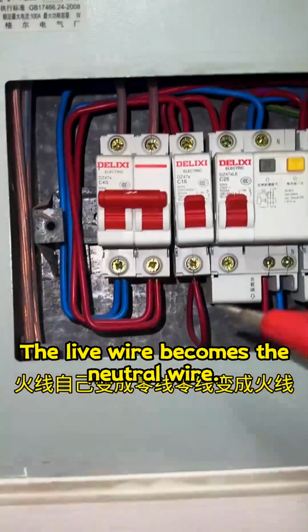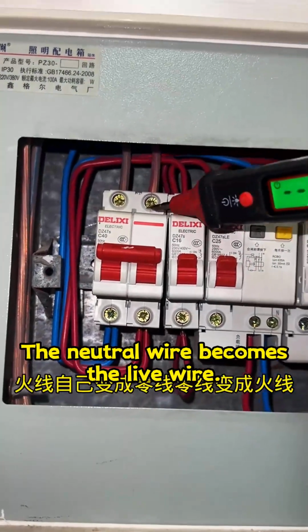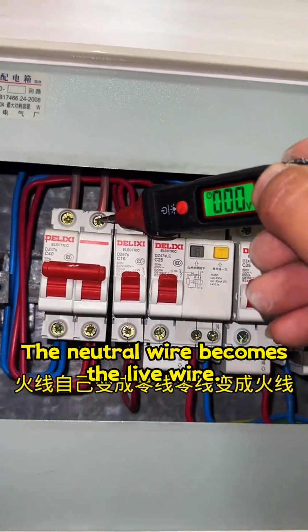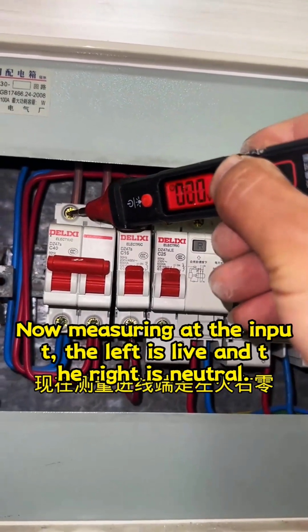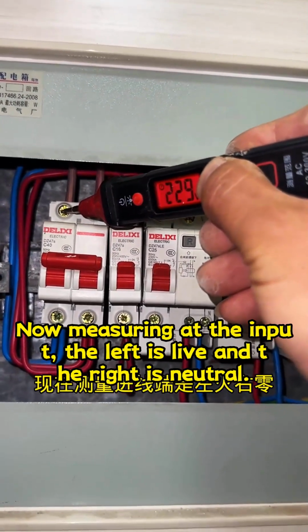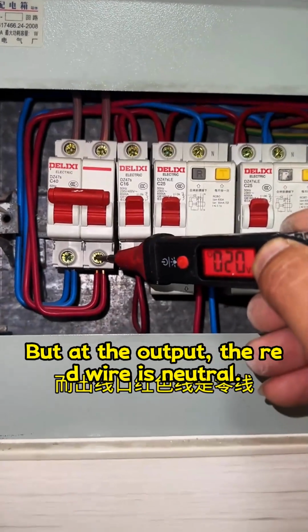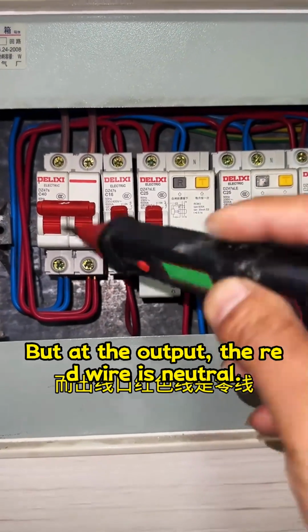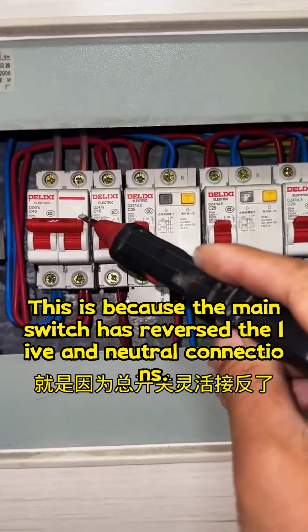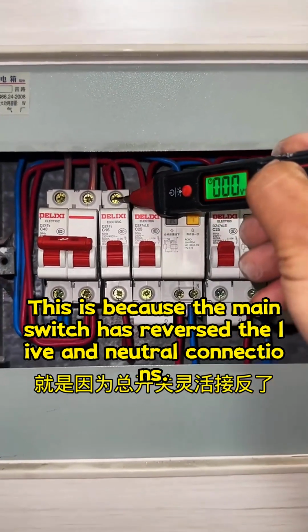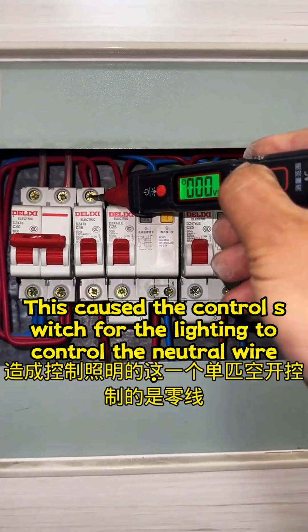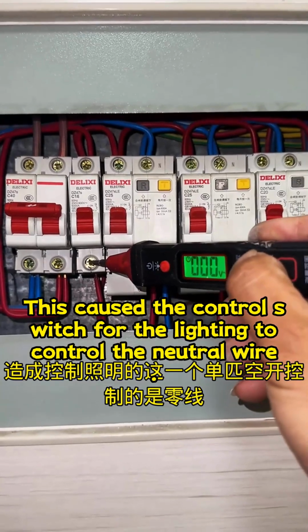The live wire becomes the neutral wire. The neutral wire becomes the live wire. Now measuring at the input, the left is live and the right is neutral. But at the output, the red wire is neutral. This is because the main switch has reversed the live and neutral connections. This caused the control switch for the lighting to control the neutral wire.